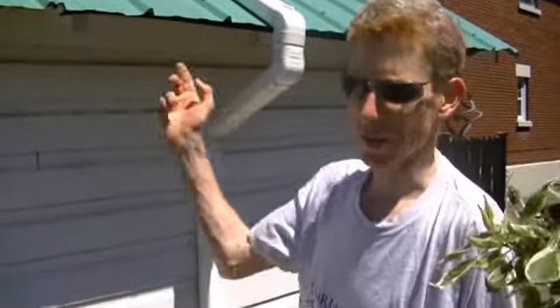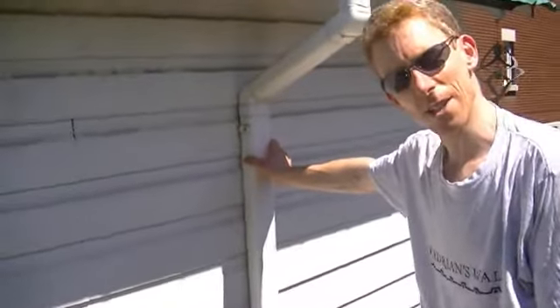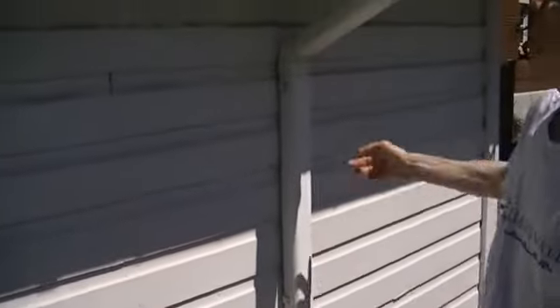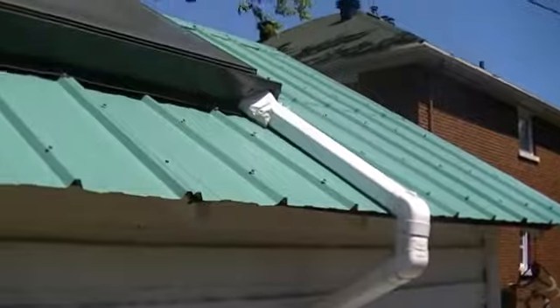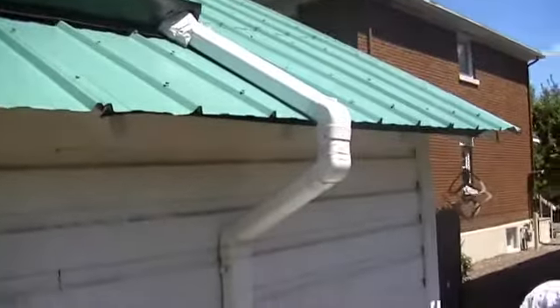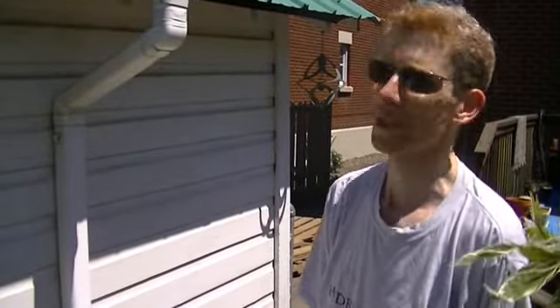It's Enerworx brand. There are generally two types of solar domestic hot water panels. This is a flat panel, so it's got a bunch of tubes going through it. This is the glycol — there are two 3/8-inch copper lines that connect the panel to the heat exchanger in the basement. There is another type which is more efficient: a series of round tubes. It does what they call passive tracking, so as the sun moves, because they're round in shape, they're able to get more heat. This one works okay in summer, spring, and fall, but in wintertime it really doesn't do much.